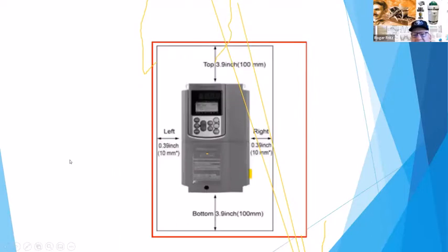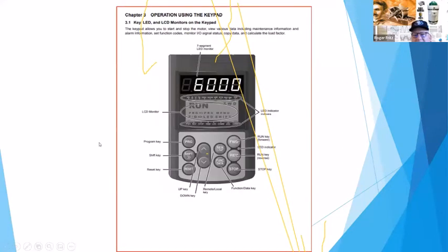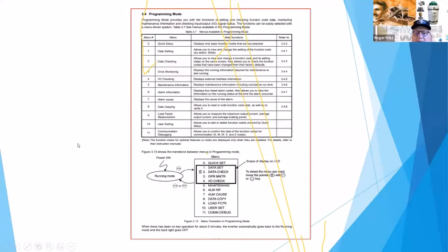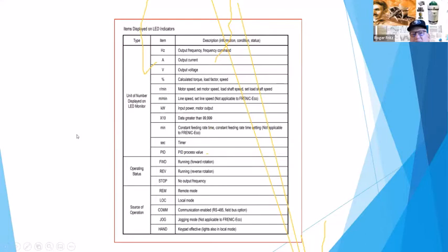One area that is important on VFDs is that we have to worry about temperature spacing, what temperature the unit is running at, because we also have the capacitors and things inside that we have to keep within tolerance. But these are some of the basic programming mode functions that are inside there. You're able to find the data set, scroll up or down with the buttons, and look for the settings. And then again, what we're back to is these basic functions of your output frequency, the output current, the voltage percentages, the output power rating that the motor is seeing. And these are display functions in most drives.